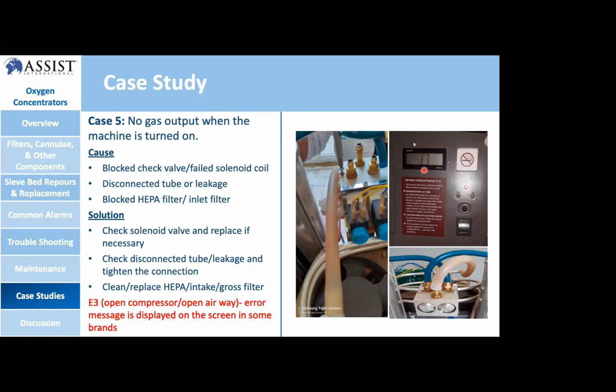So on the right part, as you have seen, we have a loosened tube, and also a solenoid one, normally disconnected tubes from the solenoid valve. Because of this, the machine is totally not giving gas at the output. It runs, but we don't get oxygen gas at the output.